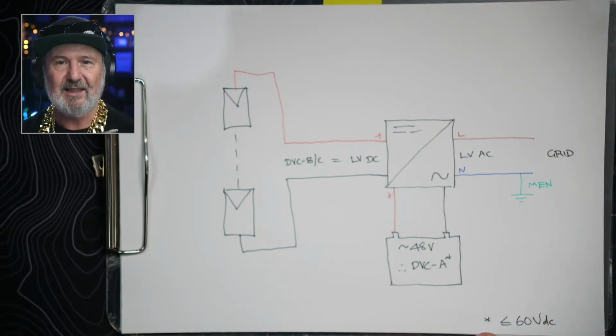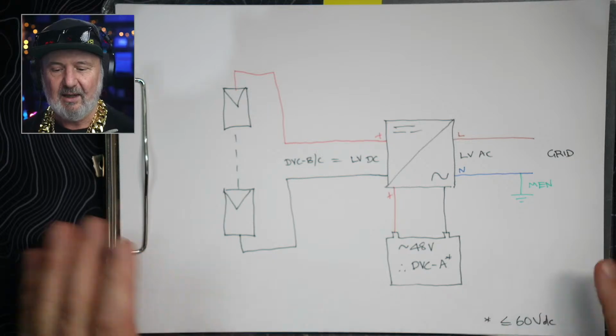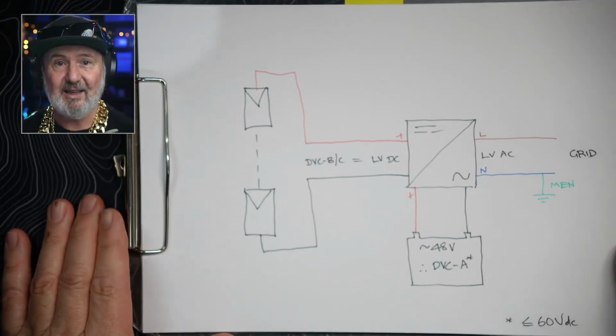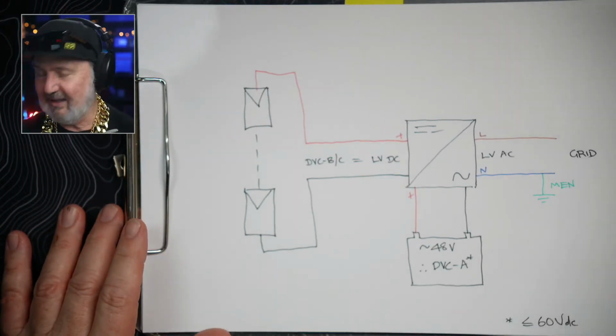It's quite an event, reverse polarizing a large electrolytic capacitor. The smoke comes out, which is quite a combustible electrolyte, and really, really bad things happen thereafter. I mean, it actually happened to me, and so I've witnessed it, and I wasn't deliberately doing it. I had a Voltronic inverter. If you've heard of that brand, they're often rebranded all sorts of names. I think this one was branded Giant, and then it was a 48-volt battery.